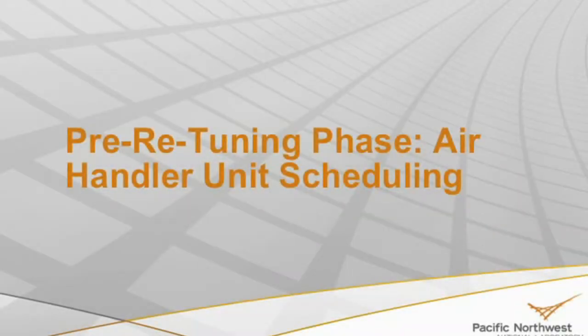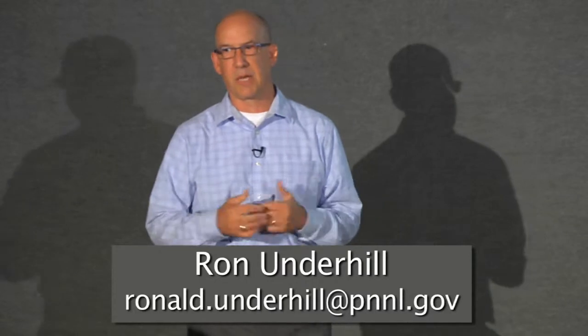We're going to get started in the next section of retuning, identifying and correcting operational problems. And we're going to talk about air handler unit scheduling. Scheduling doesn't have to be air handlers, but we'll just pick on air handlers. It could be rooftop units, it could be other things. Most BAS systems have the ability to schedule anything. Lights, set points, believe it or not, most BAS systems you can schedule set points. You can schedule terminal boxes to go into unoccupied mode.